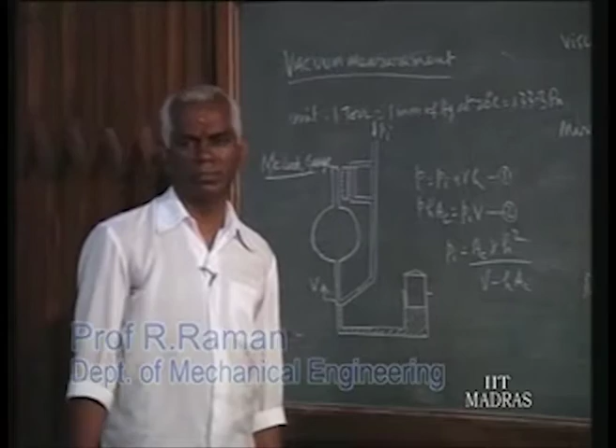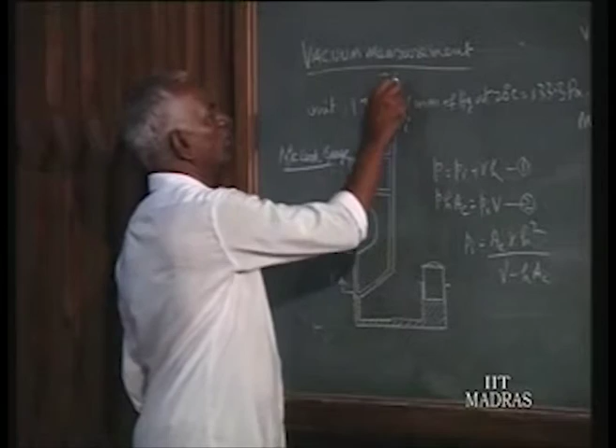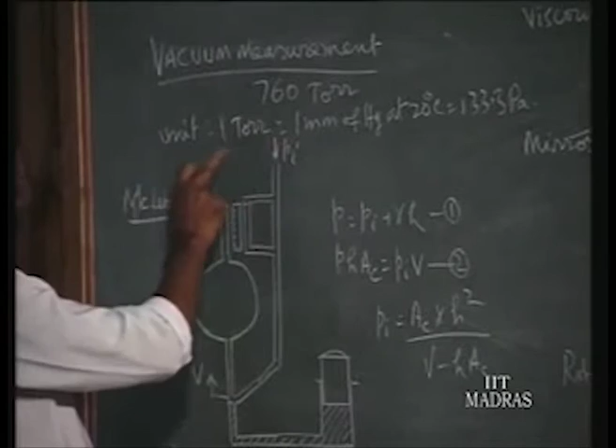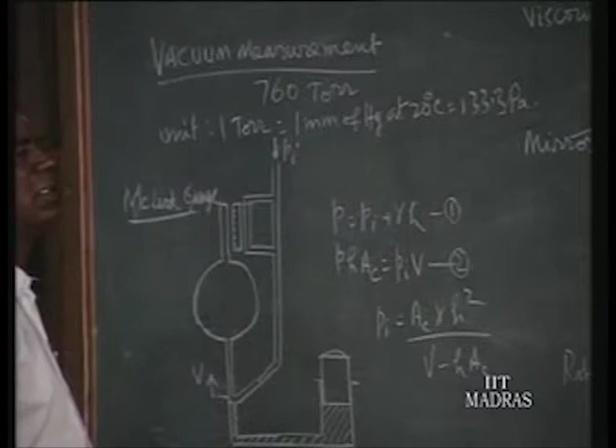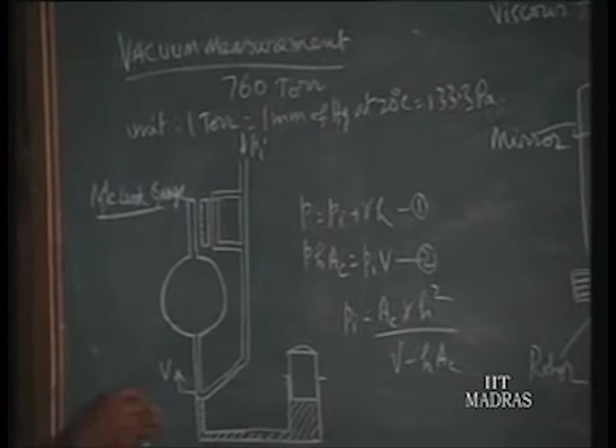Now let us learn vacuum measurement. Vacuum is low pressure. Any pressure lower than atmospheric pressure we call vacuum. Atmospheric pressure is, in another unit, 760 millimeter of mercury, or you can call it 760 torr. One millimeter of mercury is 1 torr, at a temperature of 20 degrees centigrade, and the pressure of a column of 1 millimeter of mercury is equal to 133.3 Pascal, which we call 1 torr. So atmospheric pressure we say is 760 torr, and anything lower than that we call vacuum.